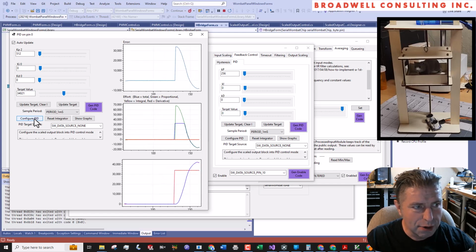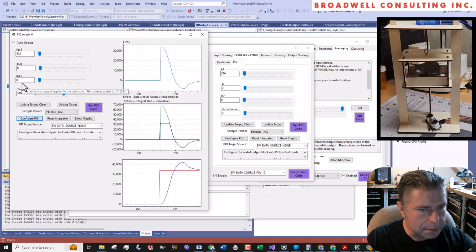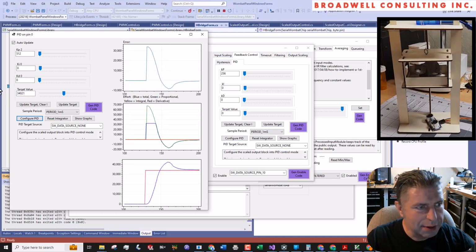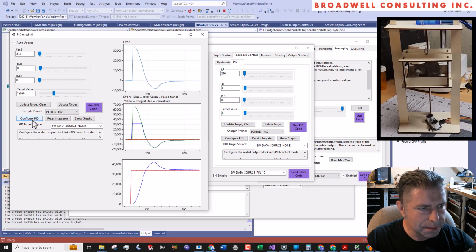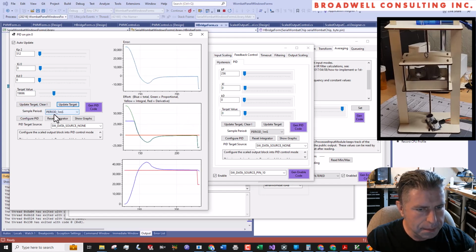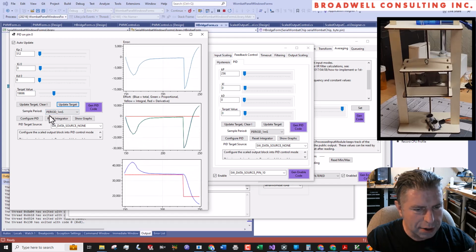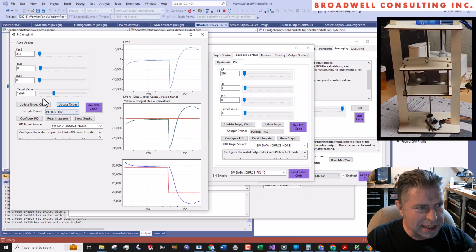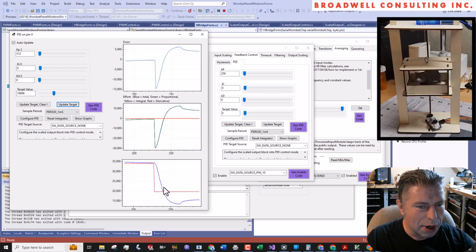And we got a lot of overshoot there. It did settle down, though. It did come back. So let's see if that's typical if we do it again. Yeah, a lot of overshoot. So that's not working real good for us because we're not getting good closing, and we're also doing a lot of overshoot. So that's not great.